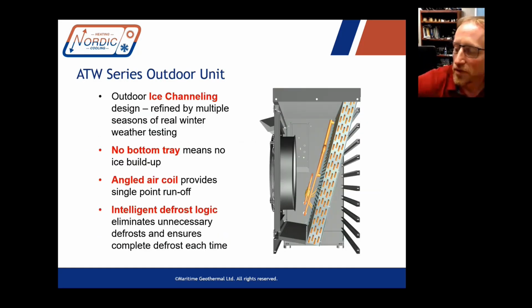All right, so when we were designing these units, I mentioned we were trying to overcome some of the problems that we heard from air source installers. One problem being experienced in the field was that usually there's a condensate tray under the air coil, and the condensate after defrost, because every air source heat pump needs to defrost due to the humidity in the air, would refreeze in the tray. First the fins at the bottom of the air coil would disintegrate, and then the ice would attack the tubing. It was very hard not to get that condensate refrozen in the drip tray. So we made the design.